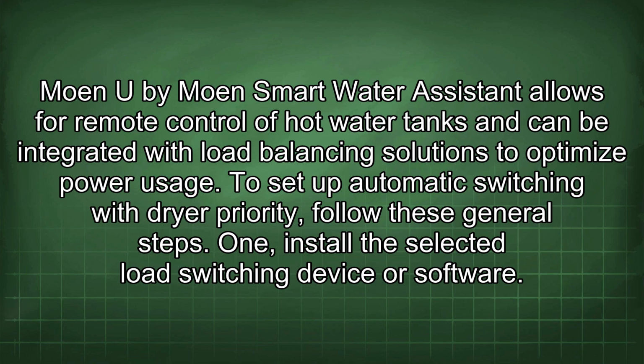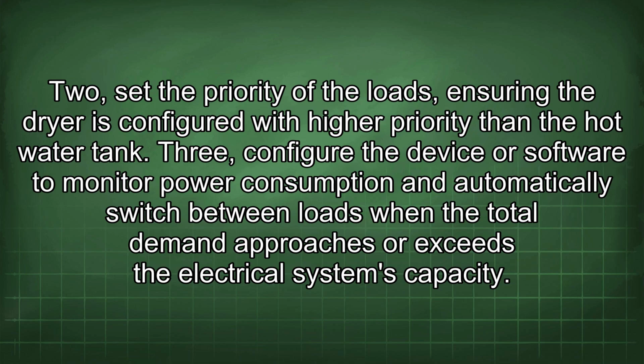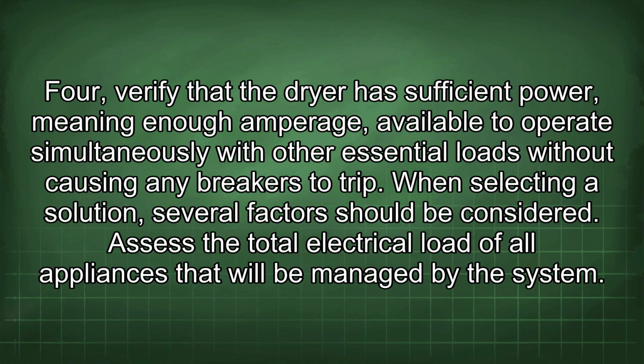To set up automatic switching with dryer priority, follow these general steps. 1. Install the selected load switching device or software. 2. Set the priority of the loads, ensuring the dryer is configured with higher priority than the hot water tank. 3. Configure the device or software to monitor power consumption and automatically switch between loads when the total demand approaches or exceeds the electrical system's capacity. 4. Verify that the dryer has sufficient power, meaning enough amperage, available to operate simultaneously with other essential loads without causing any breakers to trip.